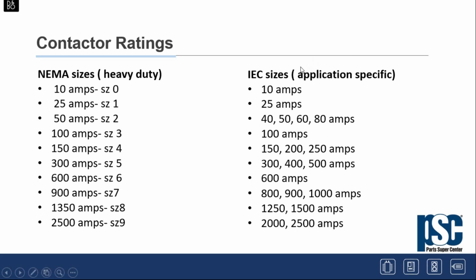On the other side, we have what I call IEC, which is the European type devices, where their ratings and applications are very specific to a specific device that they're using. So you can see ratings such as 10 amps, 25 amps, and then where NEMA would have, for example, a 40 amp or a 50 amp device for a NEMA size, you might have a 40, 50, 60, or even an 80 amp IEC rating. And as you can see from the tables, the ratings and families are not always one for one, but generally you think of the NEMA device as being heavy duty, where the IEC device is more application specific. Again, speaking in generalities here, not going to get into any specific details, but just to show you how NEMA devices relate to IEC devices.